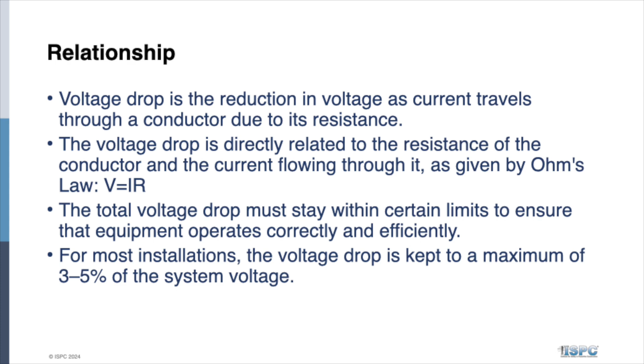Obviously the voltage drop must stay within certain limits to ensure that equipment operates quickly, correctly, and efficiently, okay? If the voltage drop is so high, it could potentially not allow those relays to operate quick enough in the case of whether it's induction or a fault or lightning or whatever the case may be that energizes our protected work area, okay? Most installations, the voltage drop maximum is 3 to 5% of the system voltage, okay? So if you're talking 12,000 volts, 69,000 volts, that's not a very large voltage drop allowable.